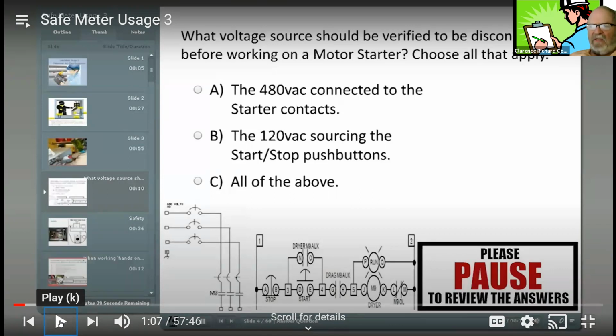You're going to have to go back to that circuit breaker panel on your wall, your 120 volt, and find out where your control circuit is. Check terminals 1 and 2 with your meter. Check to see it's got 120 volts to it and then flip it off and see it go away. If there's a transformer in each one, the breaker is going to turn off the voltage to the transformer, and consequently, you're not going to have any 120 volts power in there.